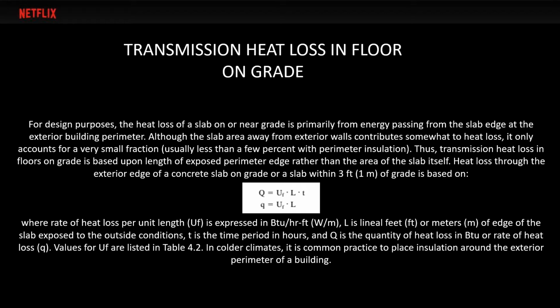Then, transmission heat loss in floors on grade. For design purposes, the heat loss of a slab on or near grade is primarily from energy passing from the slab edge at the exterior building perimeter. Although the slab area away from exterior walls contributes somewhat to heat loss, it only accounts for a very small fraction, usually less than a few percent with perimeter insulation. Thus, transmission heat loss in floors on grade is based upon the length of exposed perimeter edge rather than the area of the slab itself.